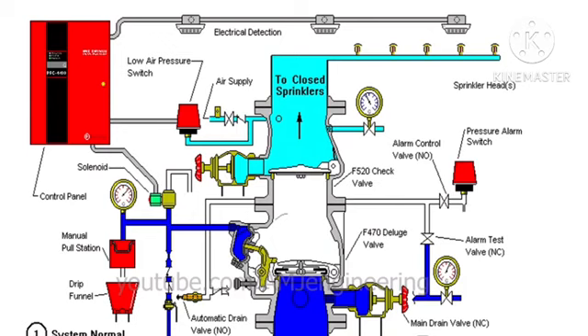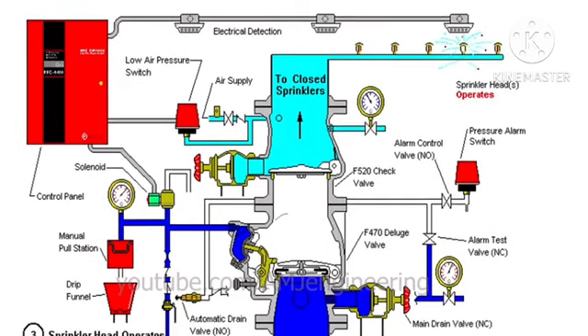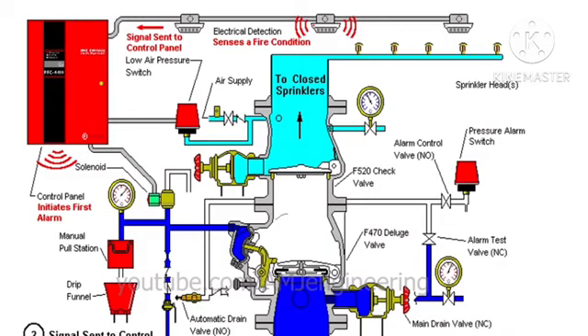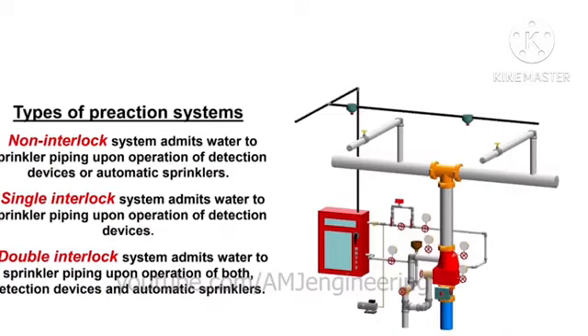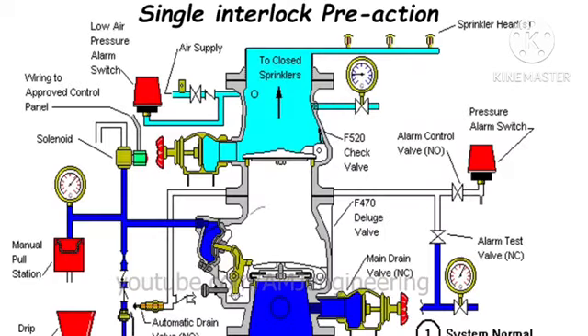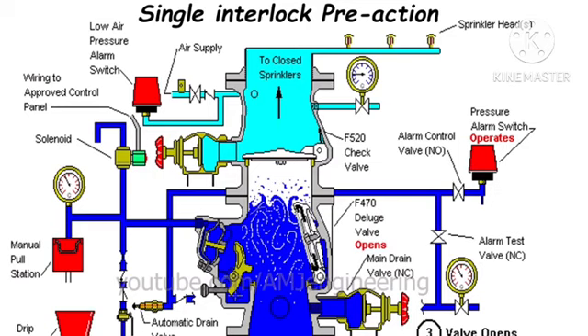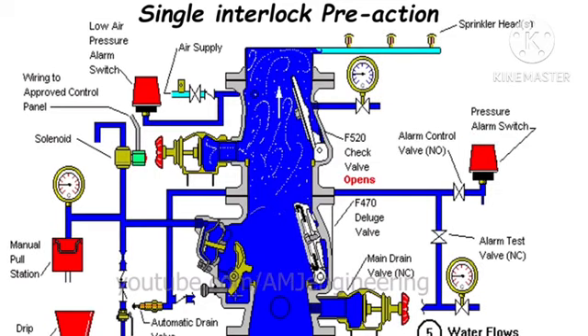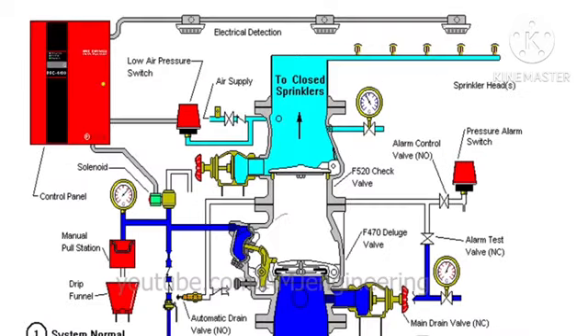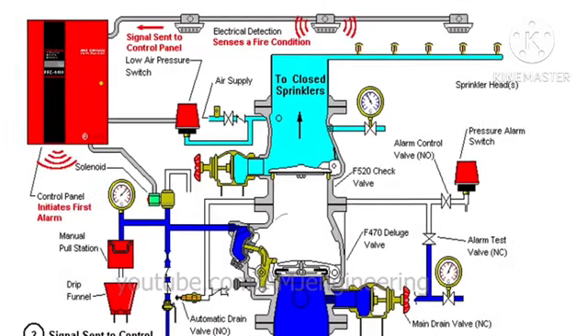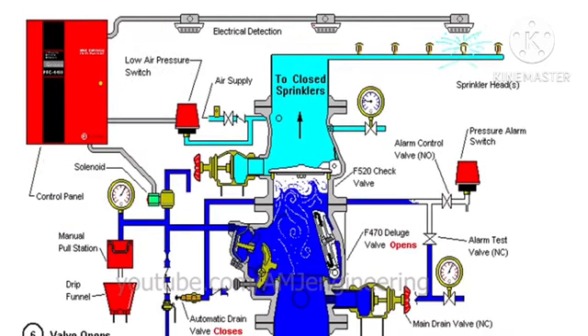Pre-action valve operation is dependent upon one or two of the following events occurring: sprinkler activation and detection device activation. A non-interlock system requires only one of either event to occur before water is admitted into the system. A single interlock system is activated only upon the event of detection device activation. However, in a double interlock system, the 2 separate events must happen before water is admitted into the system: sprinkler activation and detection device activation.